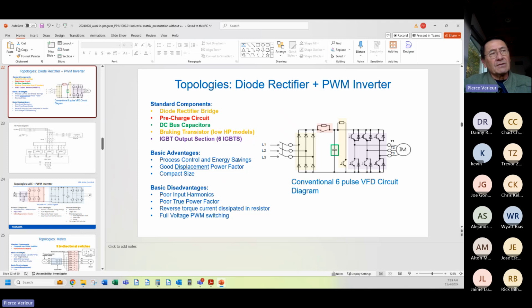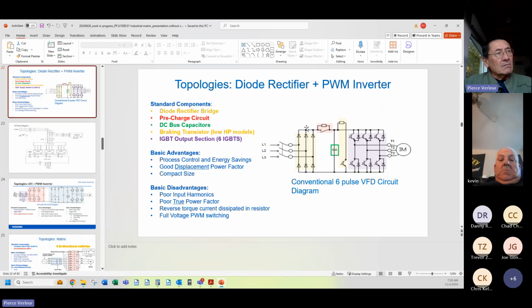You get 460, 60 hertz from the line. You want to be able to put out 230 volts, 30 hertz to make this motor go half speed. So this is an active section called the inverter, and you can control it and program it to put the voltage and frequency you want out to the motor. This is a diode bridge. There's no control of the diode bridge. These diodes in the normal variable frequency drive are not connected to the control board. They're just passive devices. They rectify AC to DC.